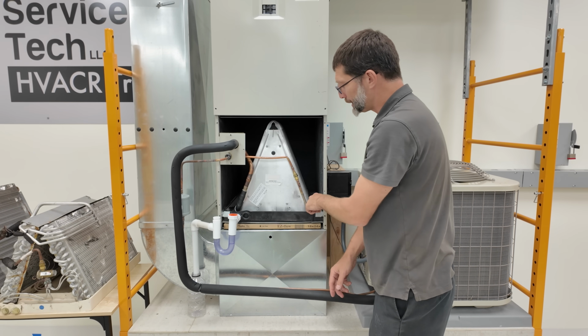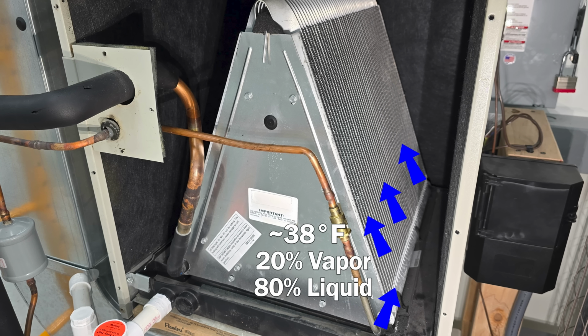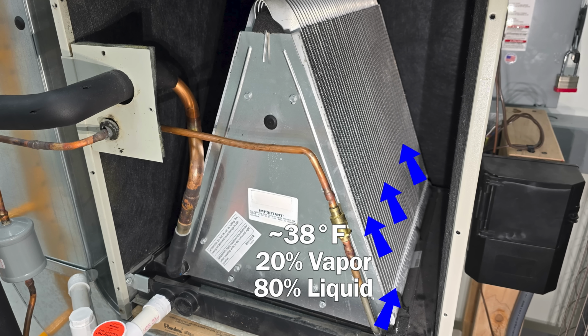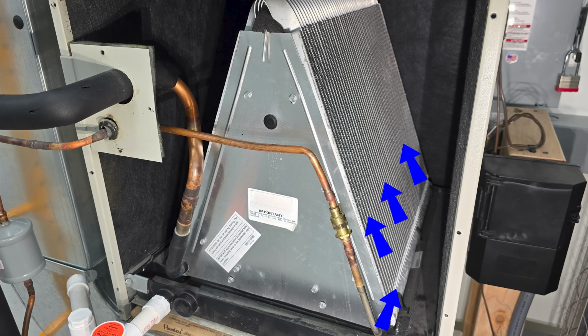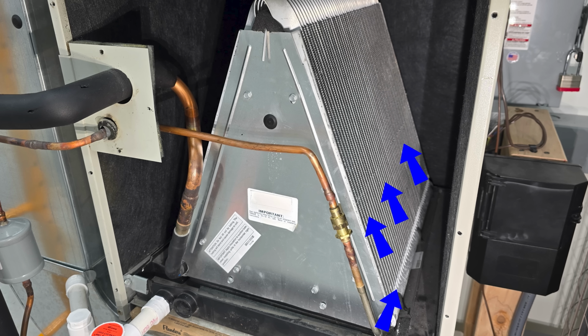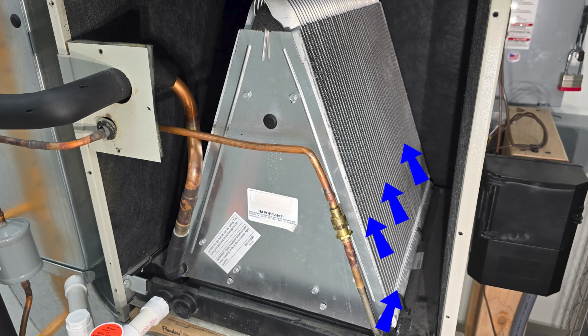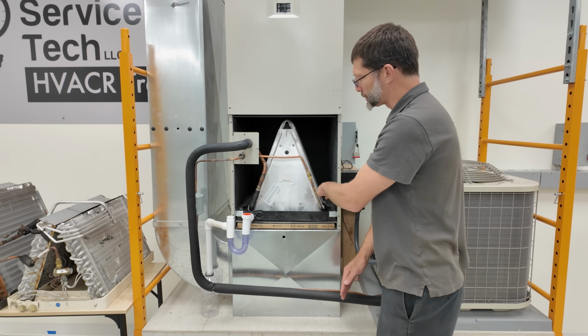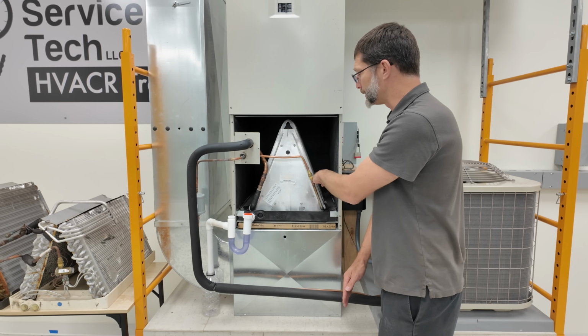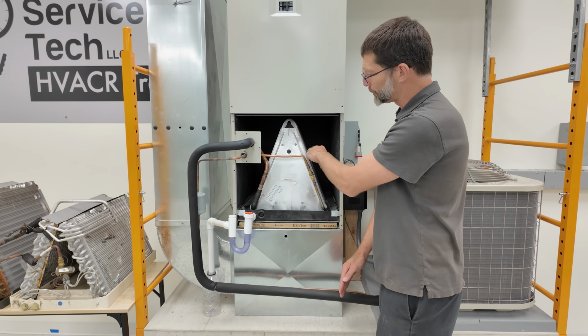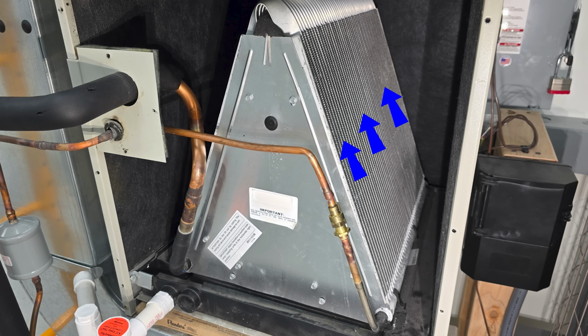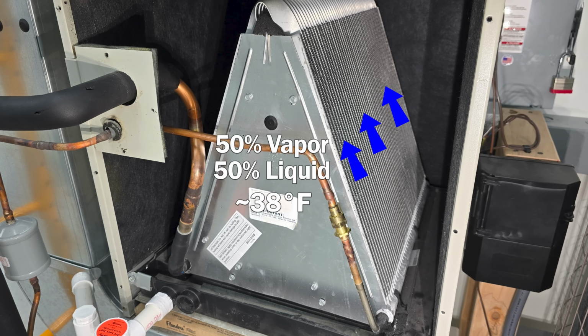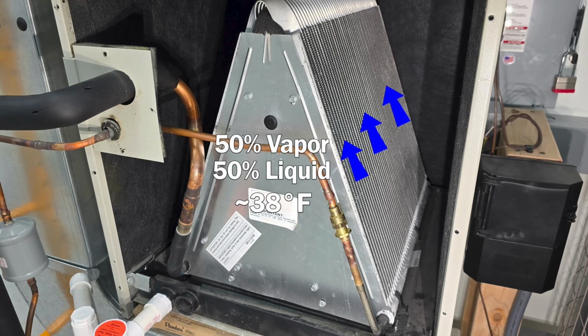It's going to be maybe, say, 20% vapor, 80% liquid as a saturated mix, and it's going to travel upwards. It's going to be maybe, say, 38 degrees or 42 degrees or something like that. It's going to stay just at that temperature as the phase change is occurring. By the time the refrigerant travels up to here, maybe it's now at a 50-50 mix, 50% vapor, 50% liquid, still at, say, 38 degrees.